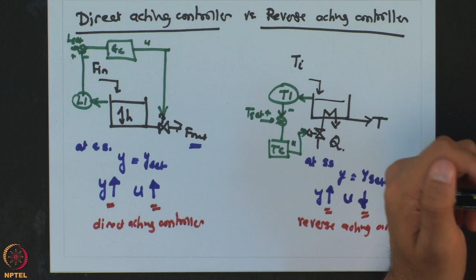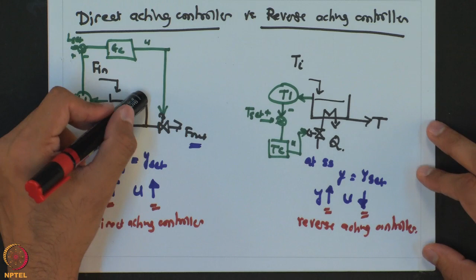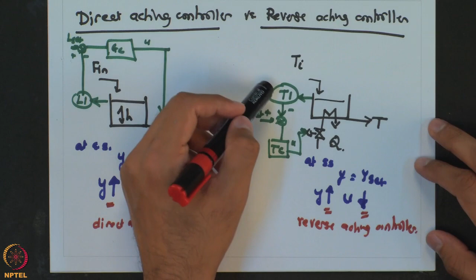So, it is very essential that you know what is the type of action of the feedback controller, whether it is direct acting or reverse acting. If you use a reverse acting controller to control this particular process, you will realize that the level will never be maintained by any type of feedback controller. Similarly, if for this particular system I use a direct acting controller, again this feedback system will never be able to maintain the temperature at its desired value. So, the first and foremost thing, before even deciding what type of feedback control action we need in terms of the proportional, integral or derivative action, is to find out whether your system is going to be direct acting or reverse acting.